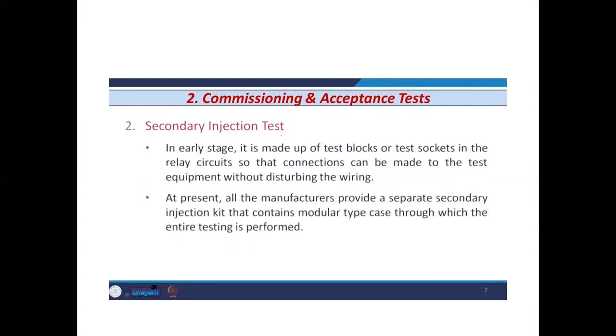In early stages, it was made up of test blocks or test sockets in the relay circuit, so that connection can be made to the test equipment without disturbing the wiring. So we do not have to disturb the wire, and we can perform some early tests. At present, all the manufacturers provide a separate secondary injection kit that contains modular type case through which the entire testing is performed.